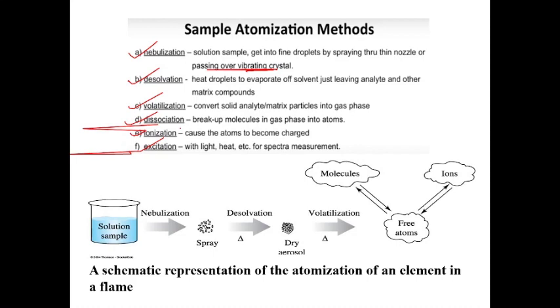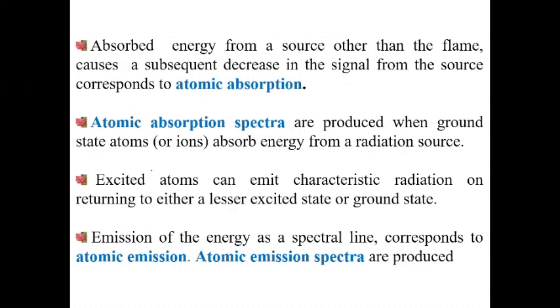Energy absorbed from a source — generally a hollow cathode lamp — causes a decrease in the signal from the source corresponding to atomic absorption. The radiation coming from the hollow cathode lamp gets attenuated, meaning its intensity decreases because it is absorbed by the atoms. That decrease in intensity is measured. Atomic absorption spectra are produced when ground-state atoms absorb energy from a radiation source.